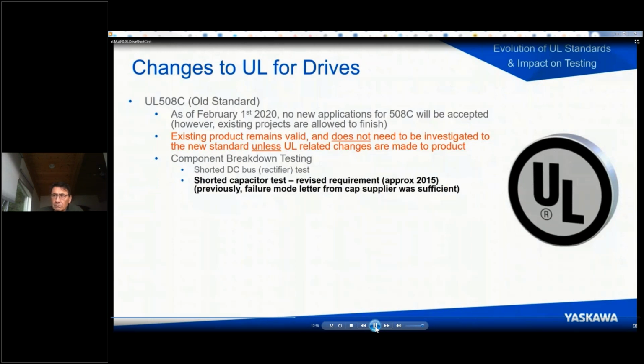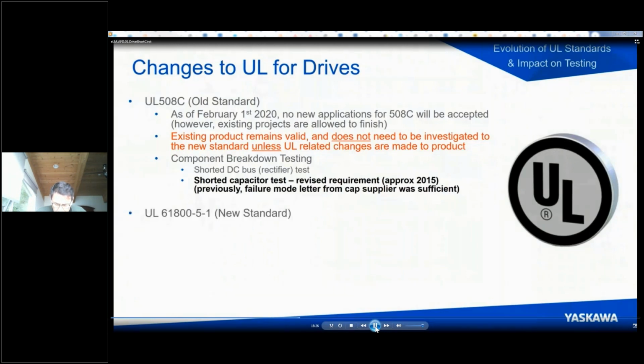Okay? Somewhere in the last 10 years, I don't know exactly when it was, so I'm saying approximately 2015, UL revised the requirement so that this test must now be performed, and a letter from the capacitor supplier stating that it was not a failure mode was no longer sufficient. Okay, so even under UL 508C, in the last 5 to 10 years, the testing has become more severe. It's very important as we release new products, and you may see some surprise differences between, say, for example, an A1000 and a G800. If they're both UL 508C, why did they have to have different rules for testing? That's because UL 508C evolved.